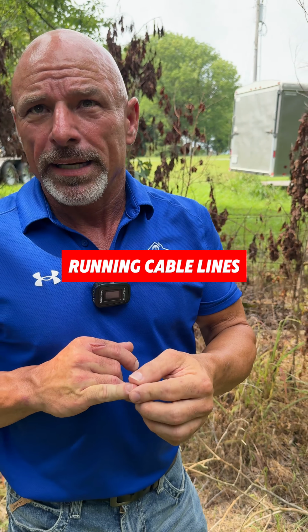It's the same as the size wire we talked about. Every foot, if you've got a number 12 wire, which is a real small wire, it's designed to carry 20 amps. But if you put 20 amps on it and run it 300 feet, the load will diminish the electricity in there, probably about 30%, if you put a bigger load on it. And it's just not going to do what you need it to do. If you're going to run it a long distance, you have to upsize that wire.